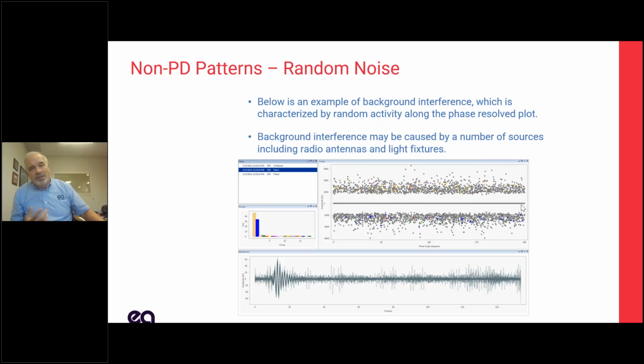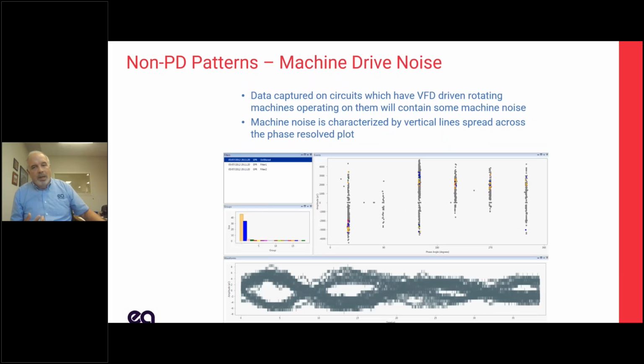If it's synchronous with the power system, it'll end up in groupings. Here's a picture where it ends up in groupings, but it ends up in 6 groupings. And they're very narrow, which means my phase angle is not moving very much back and forth. And there's 6 of them. Well, that sounds an awful lot like an inverter or a VFD or something like that. It may be synchronous with the power system, but it doesn't look anything like our first picture.